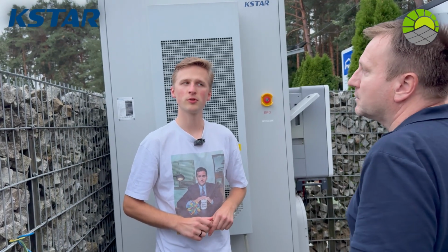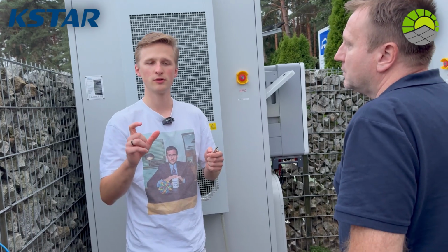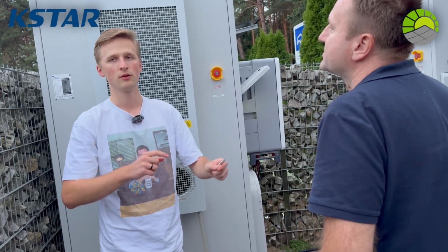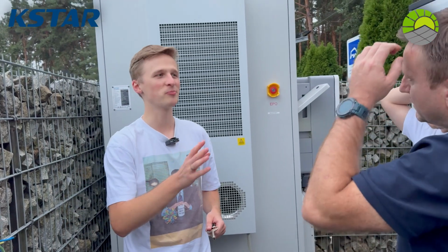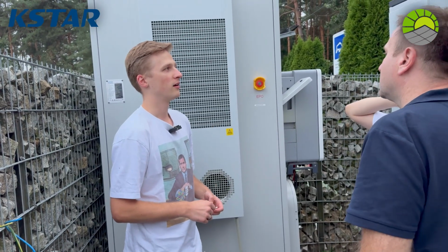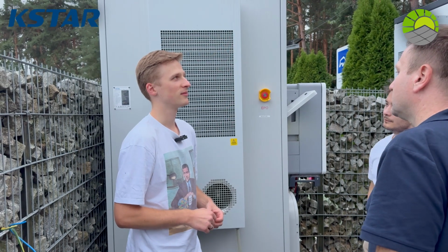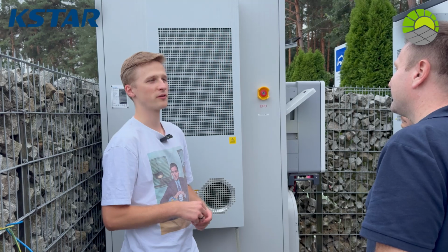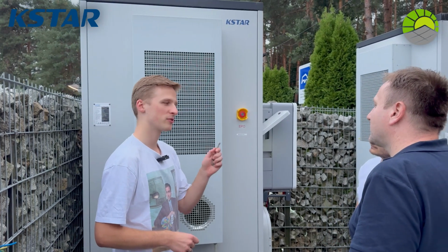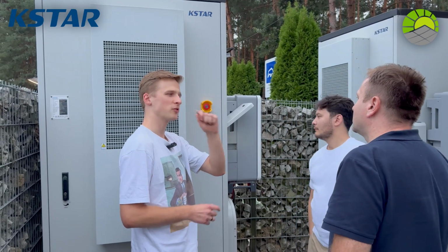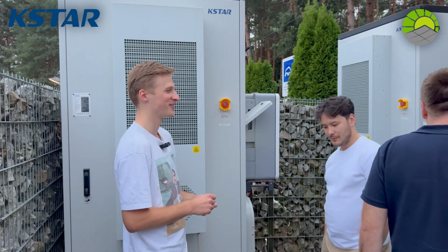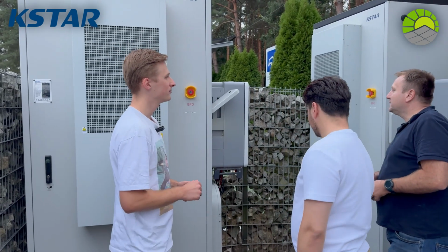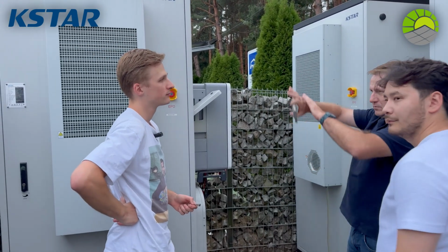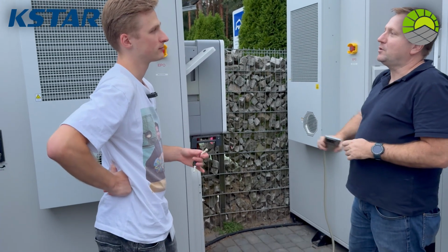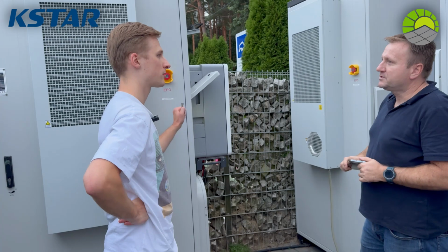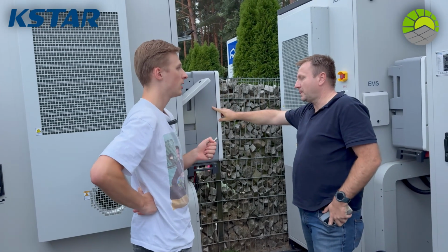But asymmetrically, how much power difference can there be? It's a PV input, 1.5 times the PV input power. I wanted to check the maximum DC power — the maximum DC is 75 kilowatts, but the inverter is 50. So you can overload it like 150 percent, but only down to a certain point.